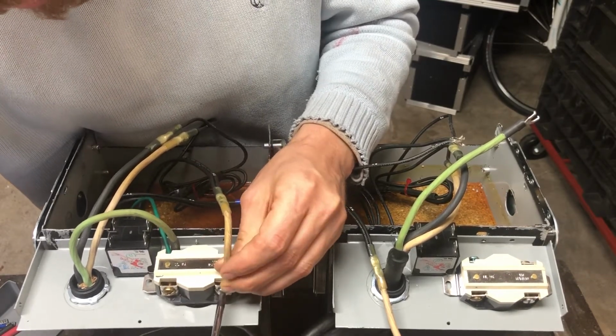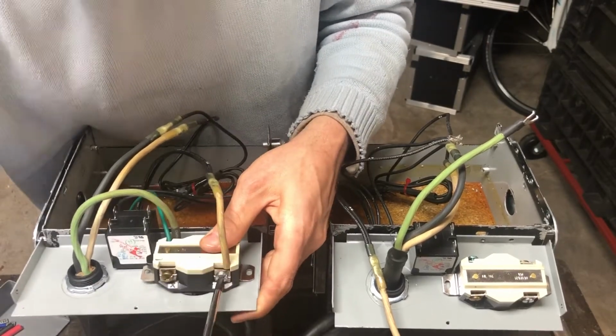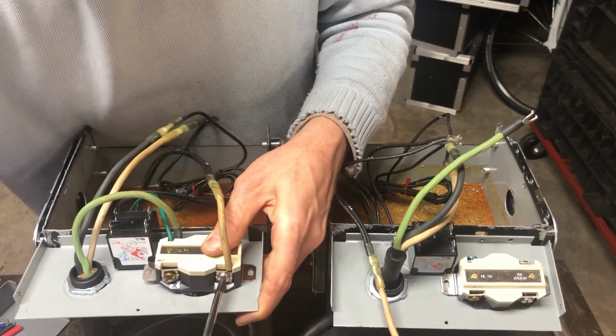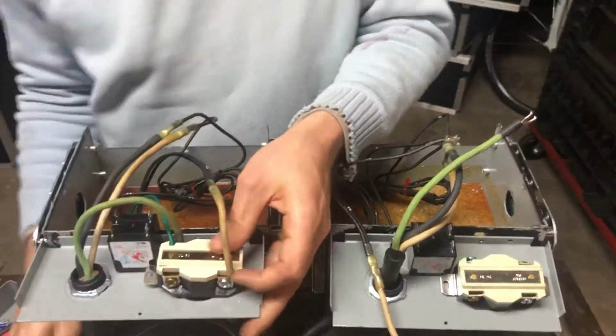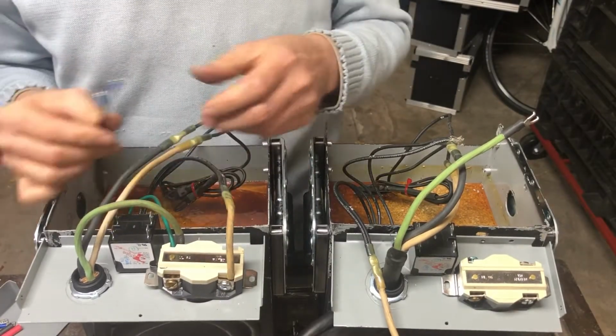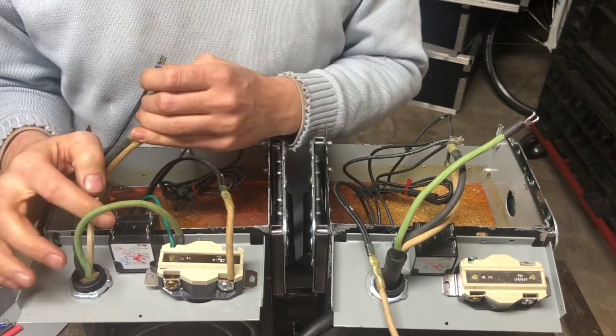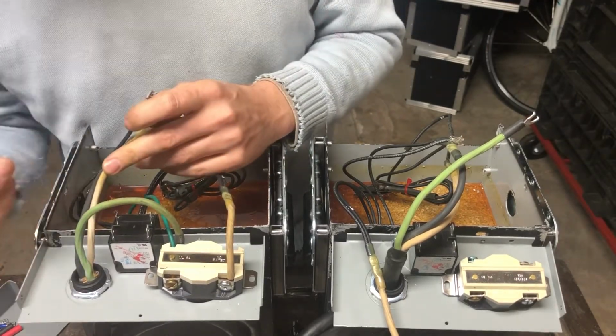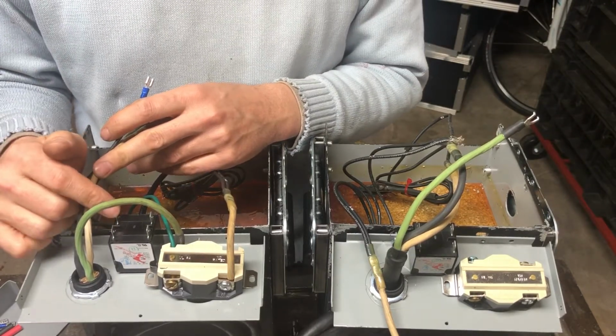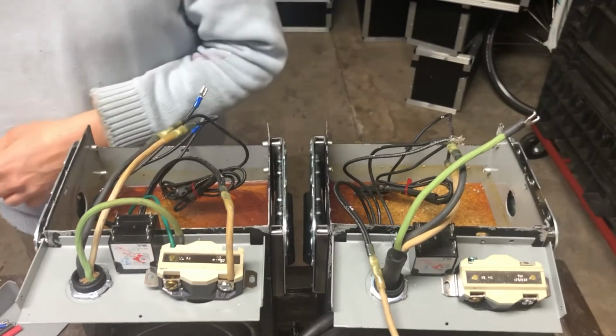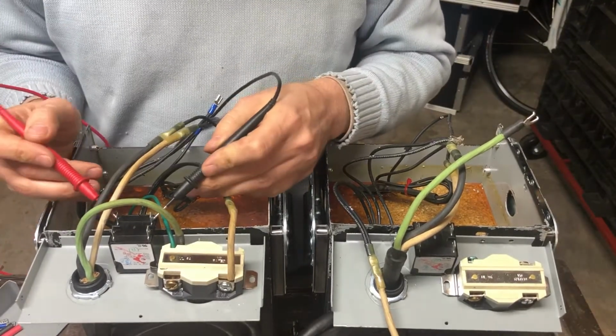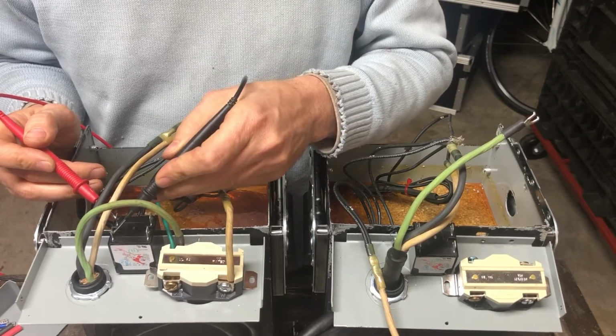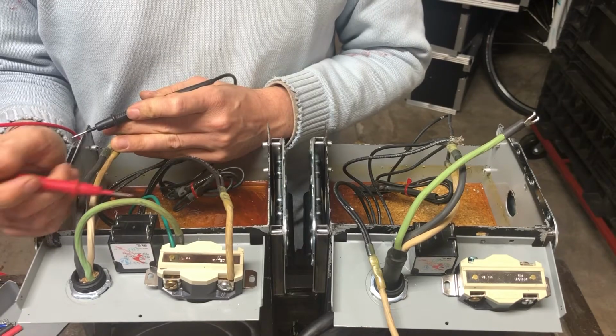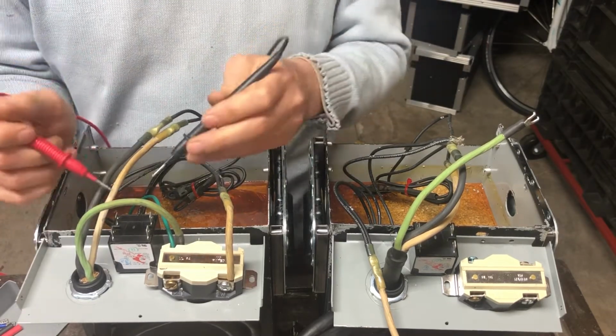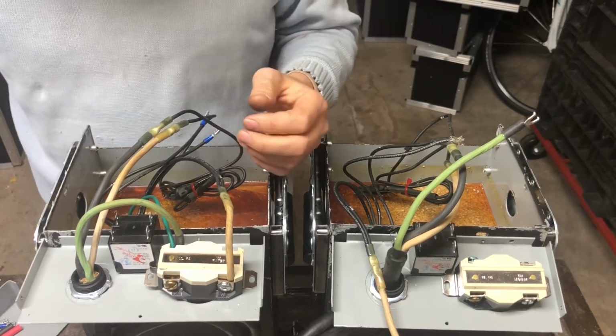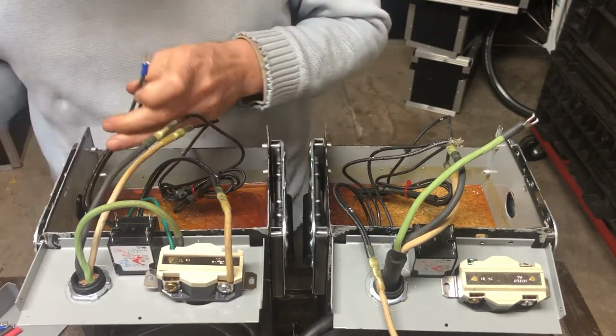So this is our neutral, or our center tap, so we'll have 120 volts from phase to neutral on these. And then our output from the transformer is going to go into the line of the circuit breaker. I can look at the circuit breaker and tell that it's oriented this way, so line is on this side and the load is on this side. But just to make sure, it's always worth checking that you have continuity this way and not this way, because if you put it incorrectly, you'll be shorting out the transformer with the circuit. So make sure anytime you hook up a device like that, that you don't have that problem.